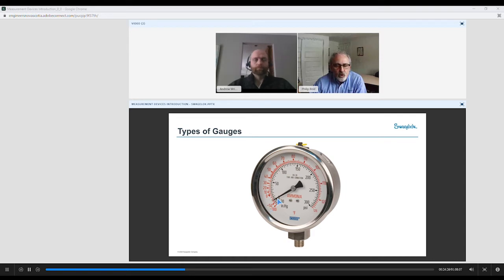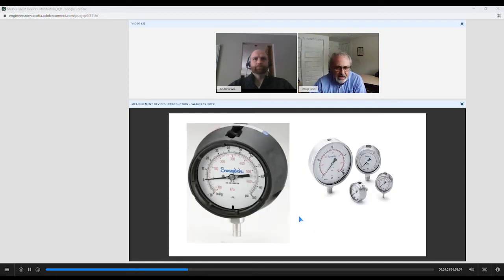So this gauge, if you were to take ammonia and put it into that situation, these would read out the correlating temperature of that specific gauge. Also, you note again the little flip lever on the top to equalize pressure inside the case. One other item I'll mention, this is a crimped front on this gauge. This front cannot be taken off to calibrate this gauge. So this gauge would not be able to be taken apart or get in to be able to calibrate.